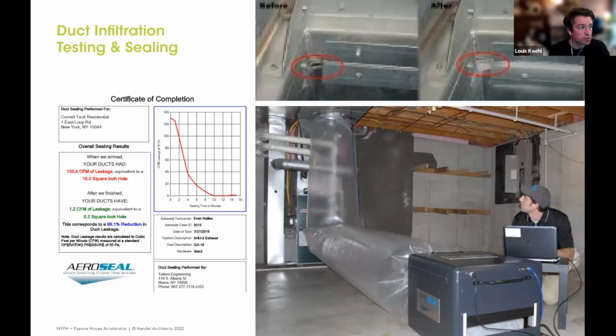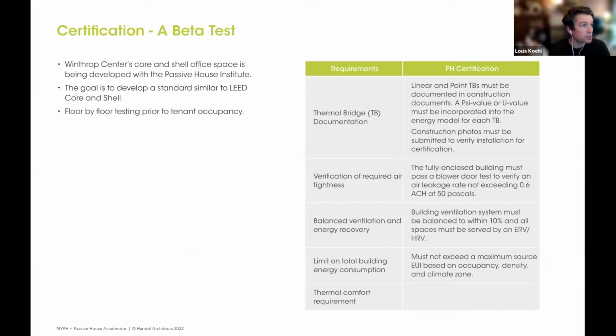All the ducts are filled with AeroSeal. AeroSeal is like an aerosol sealant that's sprayed up into the ducts when they're pressurized, and you fill the ducts with the sealant, and it finds all the holes. And you can see just the massive drop off in leakage in the ducts. This is CFM leakage before the AeroSeal install. They blow it in and they continuously test to slowly watch it drop as the sealant takes hold in all the various different cracks and crevices of the ductwork. It's a much more effective system than mechanically closing and patching all of the ductwork penetrations.